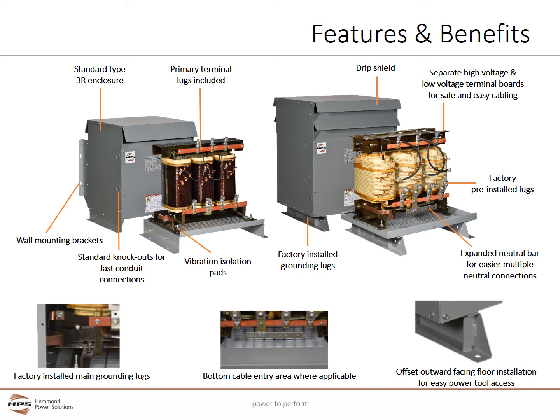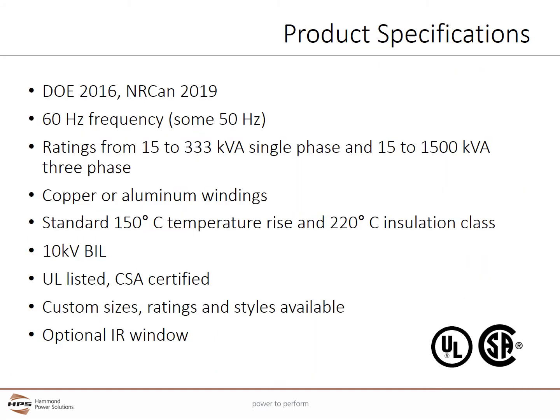The neutral bar is expanded to allow the installation of additional mechanical lugs. The primary and secondary terminal boards are separated for safe and easy cabling. The core and coil are mounted on vibration isolation pads to reduce audible noise. The HPS Sentinel-G meets U.S. DOE 2016 and Canadian NRCan 2019 efficiency regulations. Most voltages are designed for 60 Hz frequency, although some, such as 380 volt primary, are at 50 Hz.